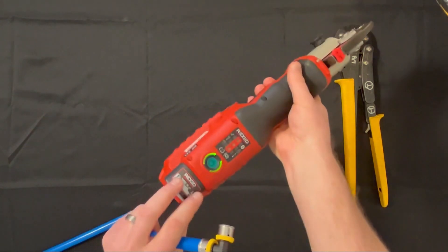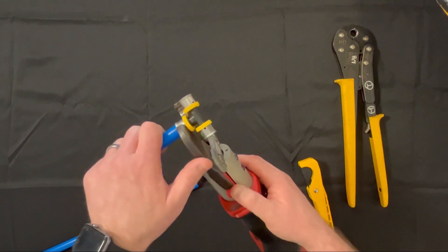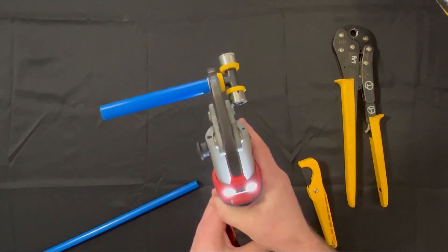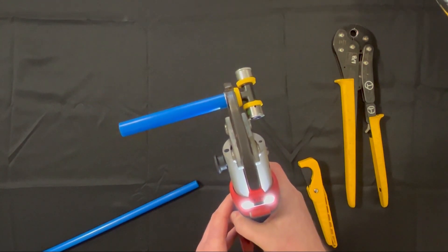First, ensure that the tool is on. Open the jaws. Place the jaws perpendicular over the sleeve up against the tool locator ring to ensure proper positioning. We will then squeeze the trigger until the press is complete.